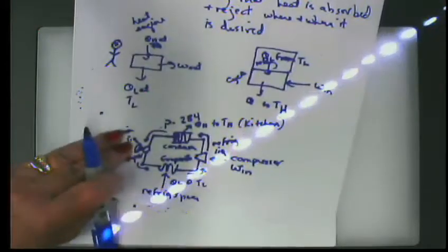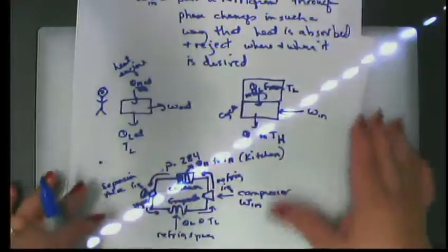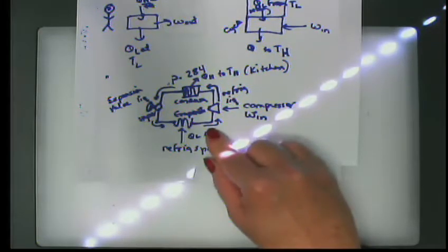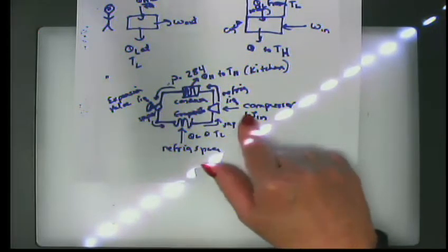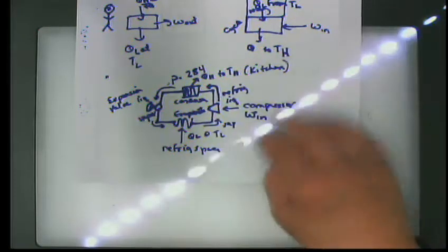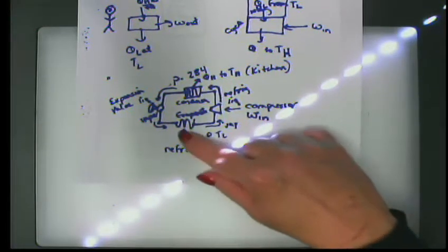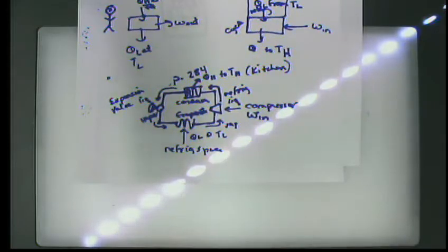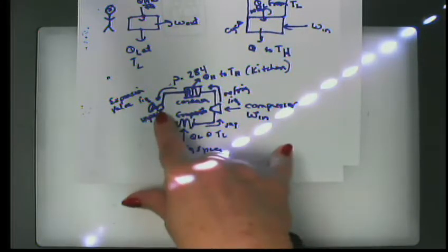Then the refrigerant continues to cycle, and there is an expansion valve at a location. The expansion valve takes a liquid and flashes it into a vapor. Then this vapor goes through an evaporator. In order for this process to occur, if you have a liquid and it becomes a vapor, vapors tend to have higher specific heats or higher H values or higher U values, so it requires energy. You force the vaporization, and then in order to maintain that state, the fluid requires heat. And since you have it positioned at the refrigerated space, where is it going to get the heat from? The only place it can get it from is the refrigerated space.